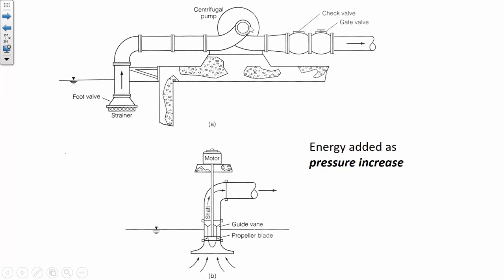One of the things in pump operations that we'll calculate in class, probably Wednesday, is the risk of cavitation. But it is something we need to be aware of, that although pressure is being added in the pump and the pressure is high on the downstream end of the pump, on the upstream end of the pump where the water is coming from, the pressure may be relatively low. And so the strategy that's used to eliminate or reduce the risk of cavitation is, number one, you don't want to have a very long suction side pipe. And the other thing is you want to minimize the elevation difference between the reservoir and where the pump is located. Because if you have an elevated pump that's really high above where you're sucking the water from, that's another thing that can reduce the pressure in the suction side hose.